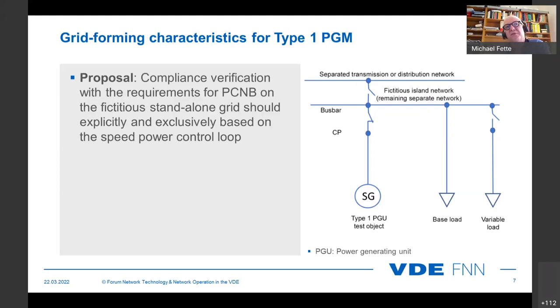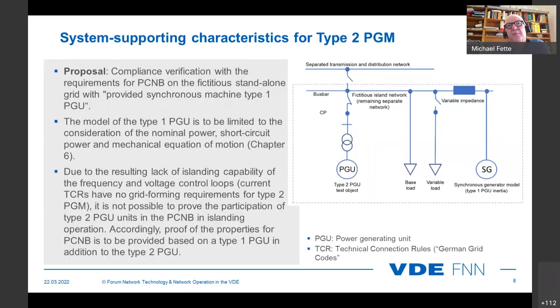The next step: if we have system supporting characteristics, it's very important to know that we have a slightly different test bed for this. We have the test machine, the inverter, the base load, the variable load, a variable impedance and a synchronous generator model, which gives only inertia. So there we have a rest system, a basic system with less inertia in this test bed, so that we can test if the controllers of the type 2 machines will also fulfill the conditions we want to see in the future.